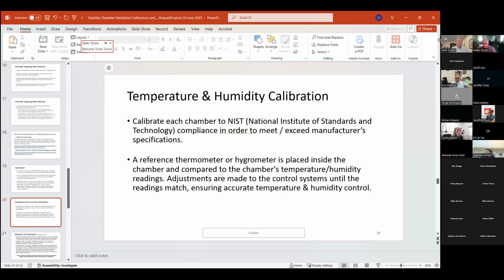And a reference thermometer or hygrometer, depending on what you're measuring, is placed inside the chamber and compared to the chamber's temperature and humidity readings. Adjustments are then made to control systems until the readings match, ensuring accurate temperature, humidity, and control. The idea here is that you're following procedures.